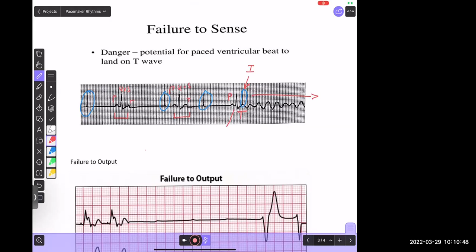Another problem that you can run into is something called failure to output. A failure to output is not the same thing as a failure to capture. A failure to output is simply that the pacemaker fails to generate an impulse. So you don't see spikes. Here we kind of catch it failing in the act. So you have a spike here, and then a QRS here, a spike here, and a QRS, a spike, no QRS. But then what happened? What have we got here?